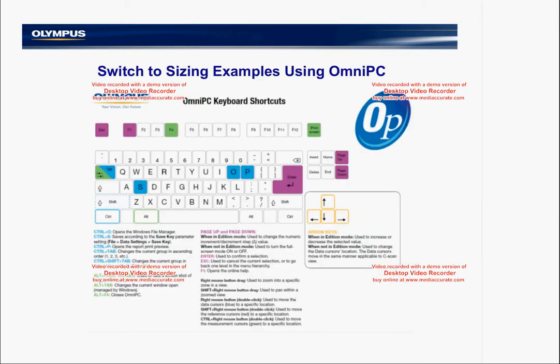Where we're going to go now is to OmniScan PC, or Omni PC. It's a new product introduced by Olympus that allows the exact same user interface from the instrument to be viewed offline on a computer. To account for the touchscreen functions, there are numerous shortcut keys and mouse functions that make analysis fast and simple. So a short training just to take over the touchscreen functions allows us to move and analyze and perform reports in Omni PC quickly and efficiently.